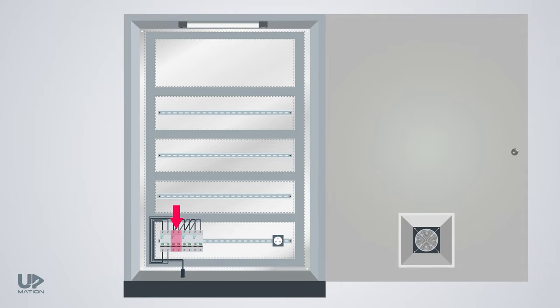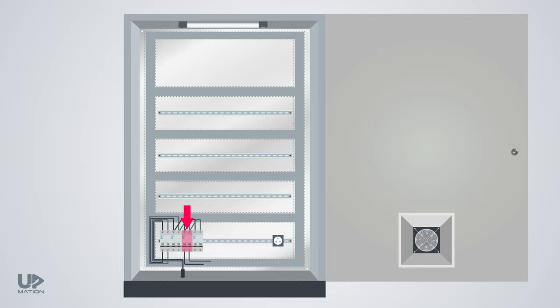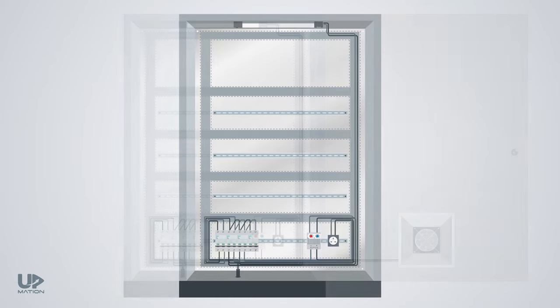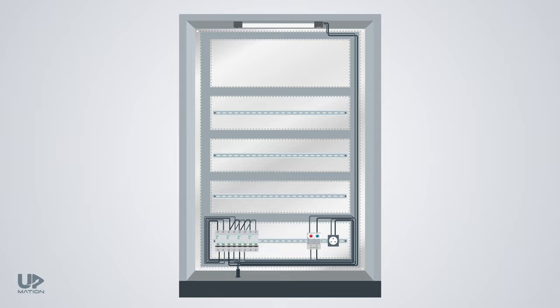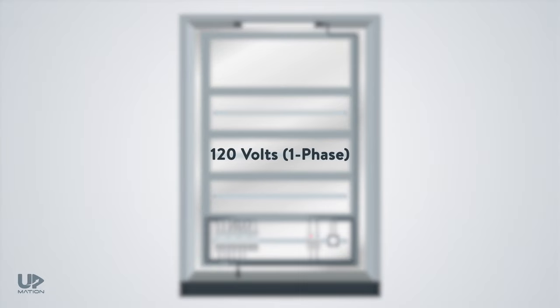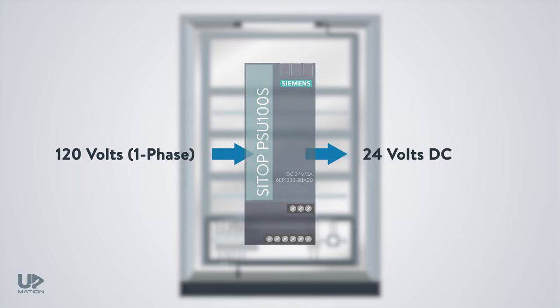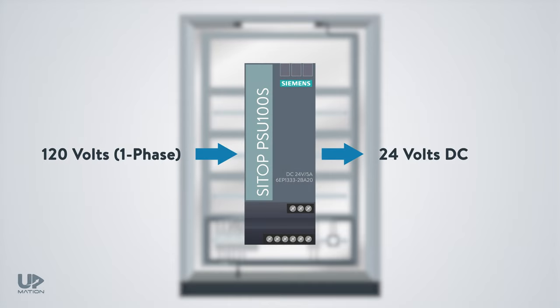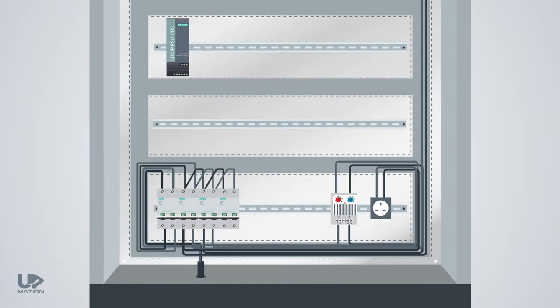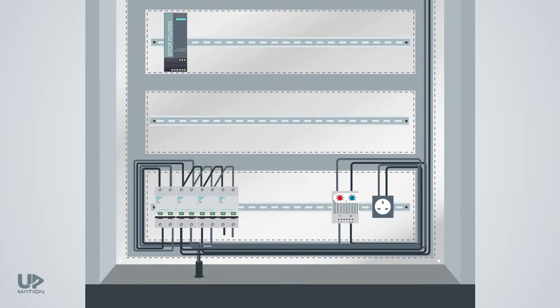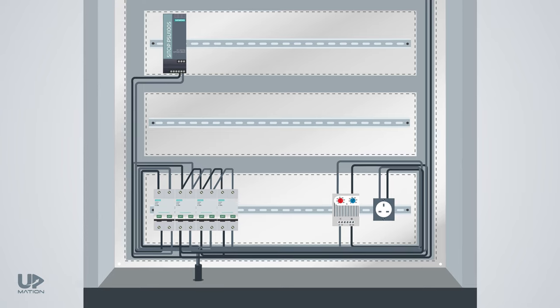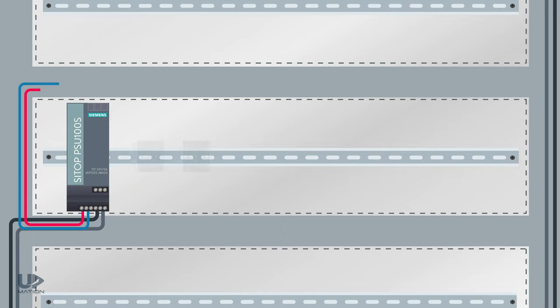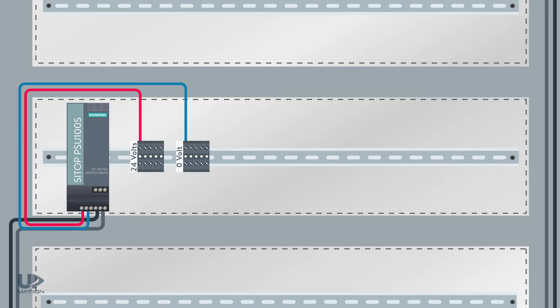This one is for the socket and the lamp. This one is for the fan. And this is for the control's power supply. To step the power down from single phase 120 volts to the control voltage, which is 24 volts for example, we need a 24 volt power supply with an appropriate amperage capacity. The next step is to connect the 120 volts to the power supply, take the 24 volts from its output, and distribute it over some terminal blocks.